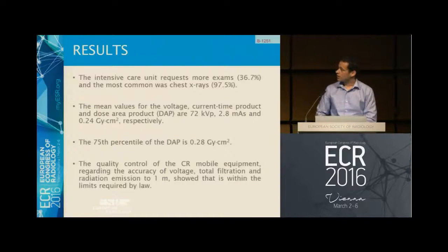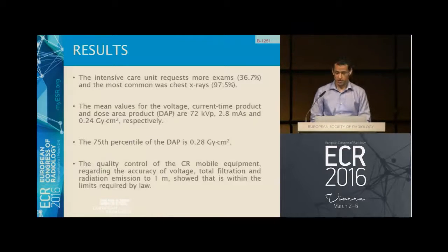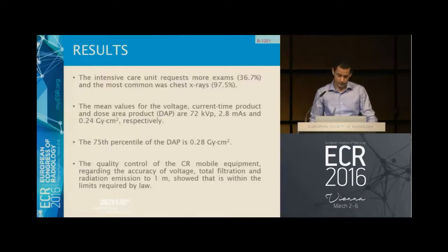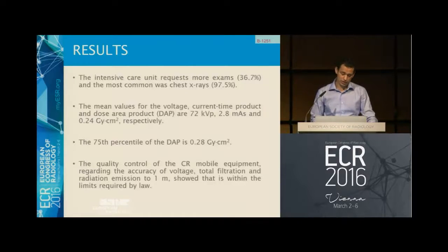Regarding our results, the intensive care unit requests the majority of exams, which are almost all chest X-rays, and the mean values for the voltage, current-time product, and dose area can be seen here. We calculated the 75th percentile of the dose area product to 0.28 gray square centimeters. We also performed quality control of the mobile equipment regarding the accuracy of voltage, total filtration, and radiation emission at one meter, and it showed that it is within the limits required by law.